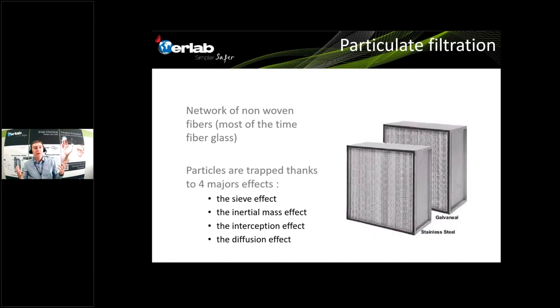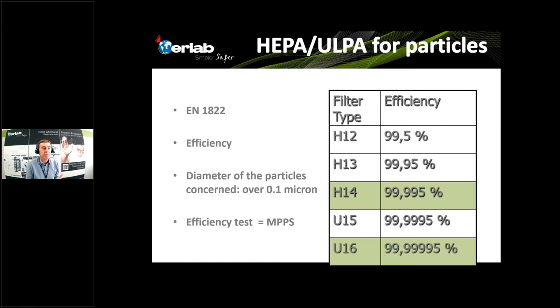The sieve effect traps particles bigger than the space between two fibers. But the other effects allow trapping particles that are smaller than the space between fibers. That is why, when we test HEPA or ULPA filters for particles, we use a complex test called MPPS — the Most Penetrating Particle Size — where we emit a mix of particles of different sizes to determine the most challenging size for the filters. This is not always the smallest particle; most of the time it is between 0.1 and 0.2 microns.